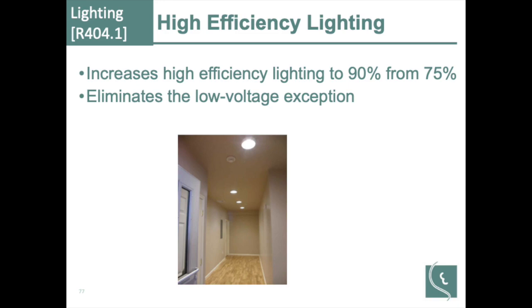But the other big change here is they have eliminated an exception. It's easy to see in a code when they add text. It's a lot harder to see when they remove it. They removed the exception for low voltage lighting. So now all that track lighting that used to be, oh, I just put it on low voltage and it doesn't count towards my 75%, it doesn't count towards my 25% allowance. Now it all counts.